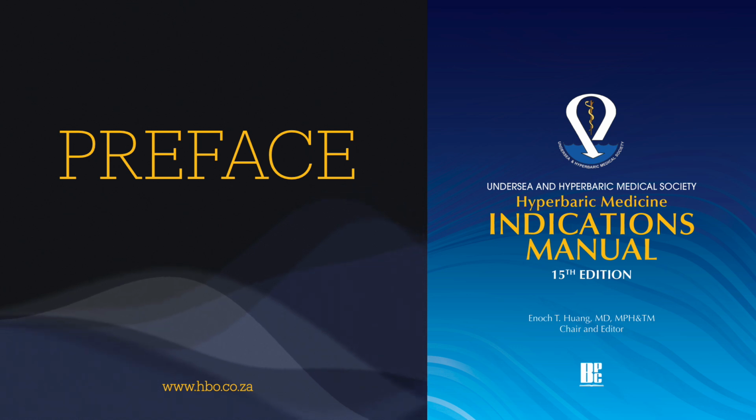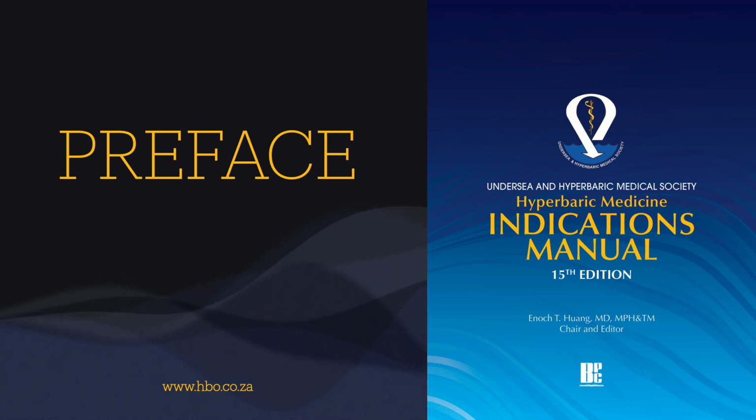So let's quickly recap that precise definition from the manual. A standard, safe, effective HBO session according to UHMS needs: physician prescription oversight, whole-body treatment in a hard-sided chamber certified to ASME PVHO-1 and NFPA 99, pressure of at least 2.0 ATA, 202.65 kPa, breathing medical-grade oxygen equals 99.0% pure, and a duration typically 90 to 120 minutes. That's the blueprint. That set of criteria is the fundamental definition provided by the UHMS, and it's what differentiates legitimate therapy from, well, other practices.